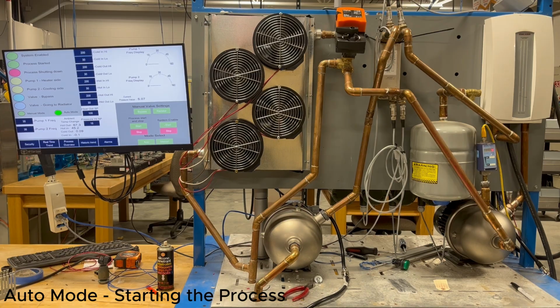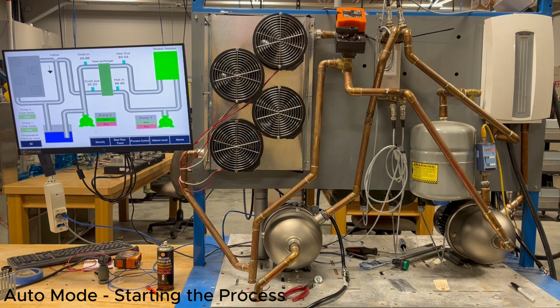So in order to start our process in auto mode, we need to have the system enabled and then hit our start process button. Then our pumps will run at the set point frequency we gave them. Because our hot out thermometer probe is below the heat set point, the valve will send water through the bypass. Then once the heat set point value is met, the valve will start turning to direct flow to the radiator, and the fans will stage on and off depending on how hot or cool the water is relative to the desired set point. And the process will continue to run like this until the shutdown sequence has started.